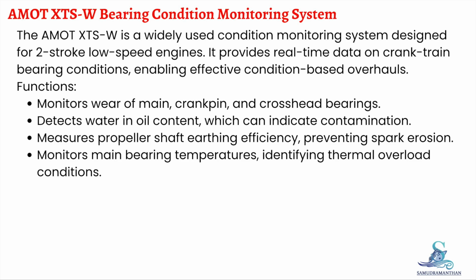The AMOT XTS-W continuously monitors wear of the main bearings, crankpin bearings, and crosshead bearings. In addition, it can detect water in oil, monitor propeller shaft earthing efficiency to prevent spark erosion, and track main bearing temperatures to identify early thermal overload conditions. In short, it gives engineers real-time insight into the health of the entire crank train.